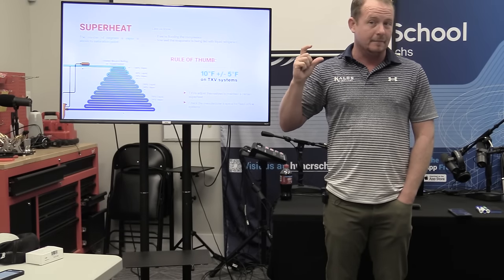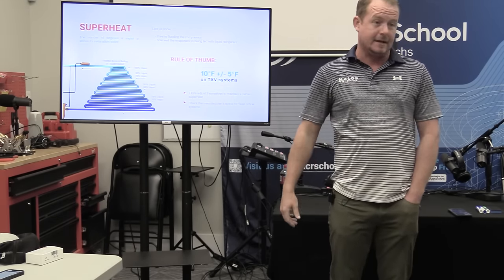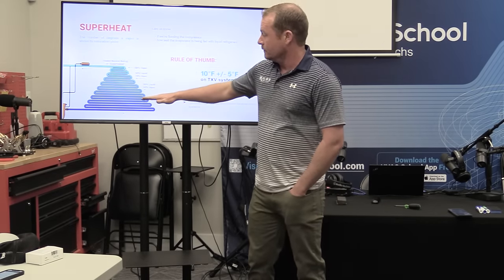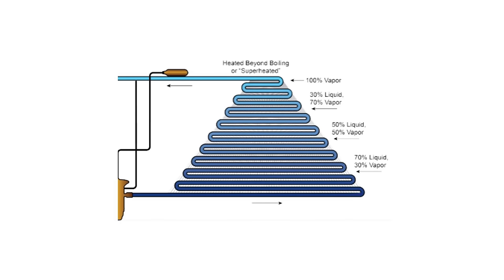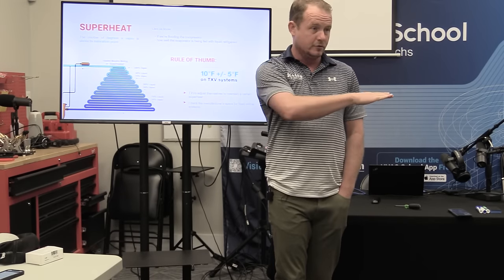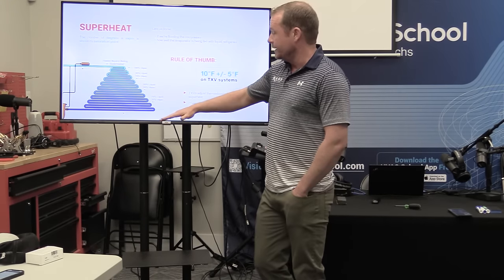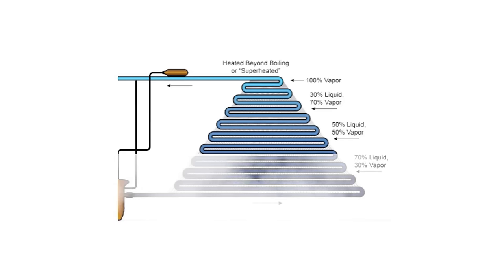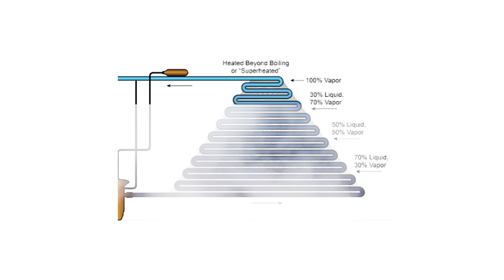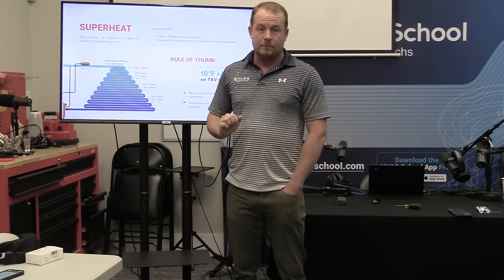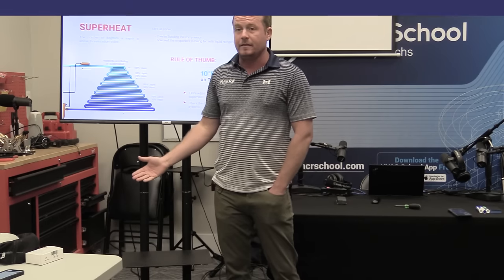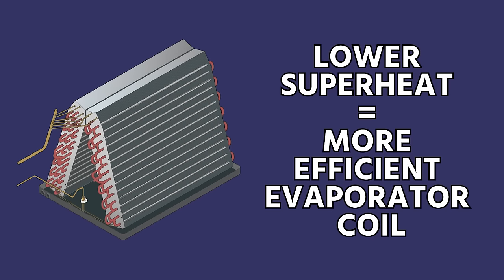If superheat is a low number, that means it picked up very little heat by the time you measured it outside. If it's a high number, it picked up a lot of heat — which tells us it's not getting enough liquid. How full is the evaporator coil with boiling refrigerant? More boiling refrigerant is better. Lower superheat equals a more efficient evaporator coil.